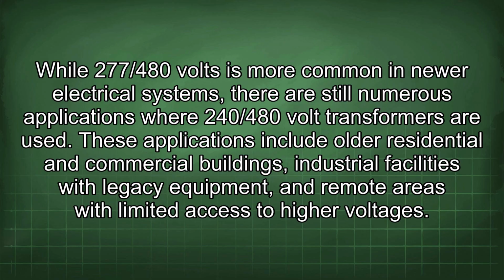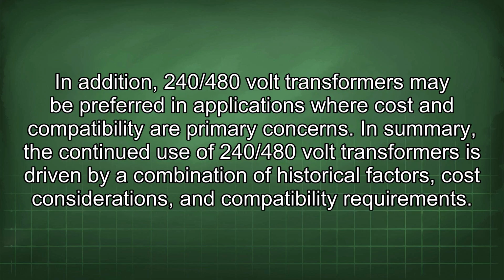While 277/480 volts is more common in newer electrical systems, there are still numerous applications where 240/480 volt transformers are used. These applications include older residential and commercial buildings, industrial facilities with legacy equipment, and remote areas with limited access to higher voltages. In addition, 240/480 volt transformers may be preferred in applications where cost and compatibility are primary concerns.